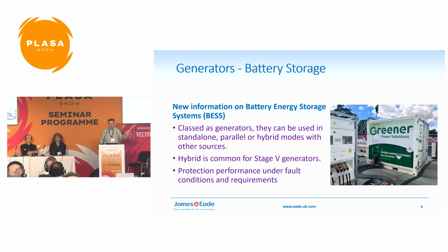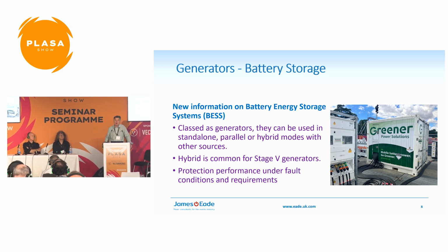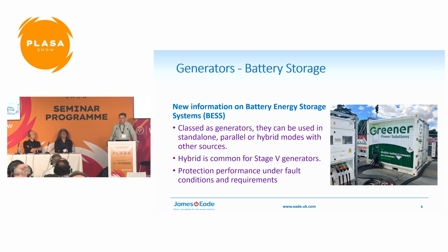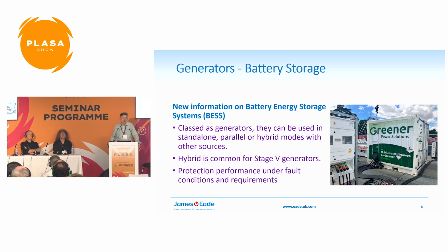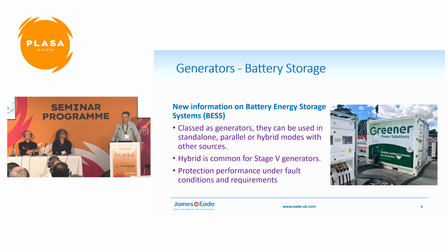So there's more commentary on that, in particular the fault modes, because one of the challenges with battery storage units is knowing what will happen if someone actually drops a crowbar across the output, because generally the electronics doesn't have the ability to deliver the fault currents required to operate protection. So usually the electronics will shut the system down within an allotted time. So it's important to get from the manufacturer how that will work and what happens when you have these systems paralleled up in operation. Hybrid modes are also discussed as well.